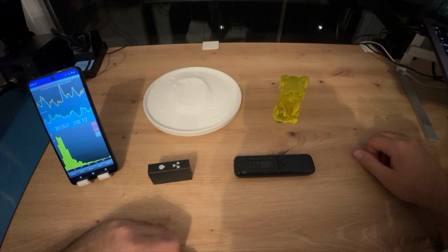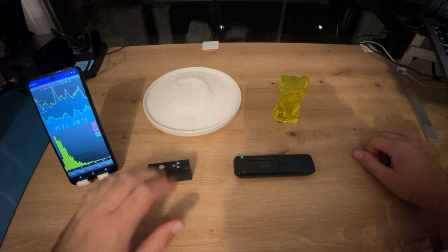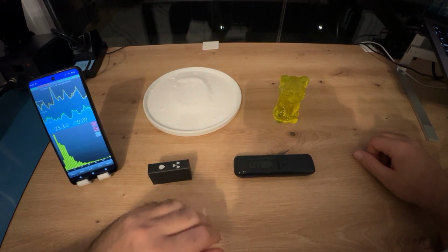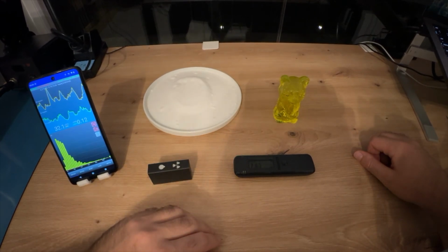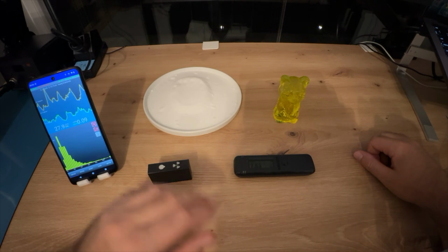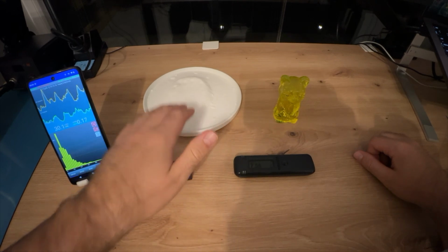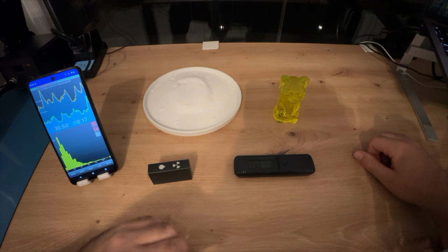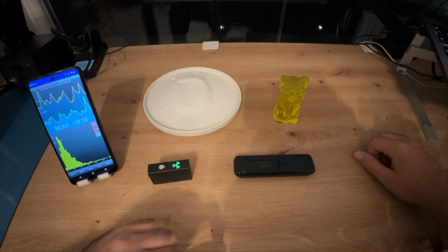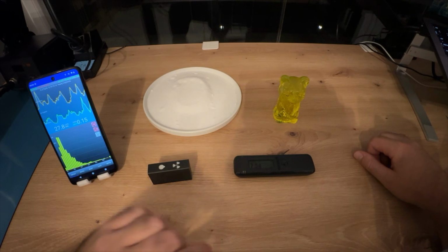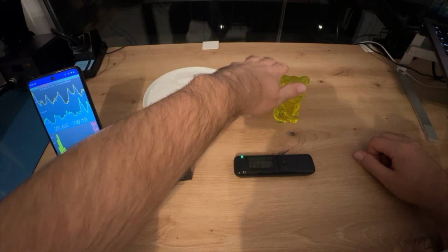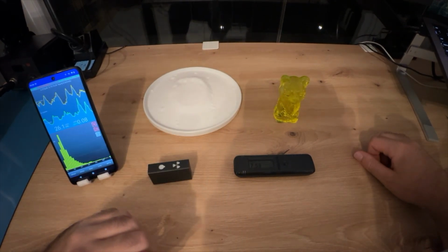Since we went through the basics of the scintillation devices world, we can move on to the testing of the two mentioned products, Raysid and Radiacode 103. I have prepared two simple tests to compare the devices, one with NORMs, that is, naturally occurring radioactive materials that are the source of our natural background radiation, and a sample of uranium glass that contains low amounts of uranium.